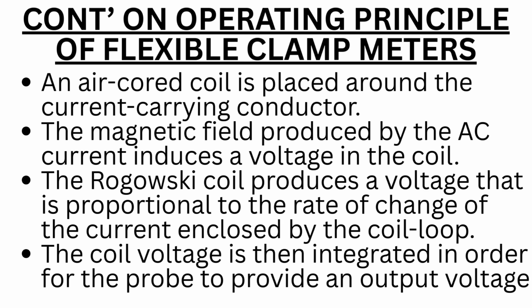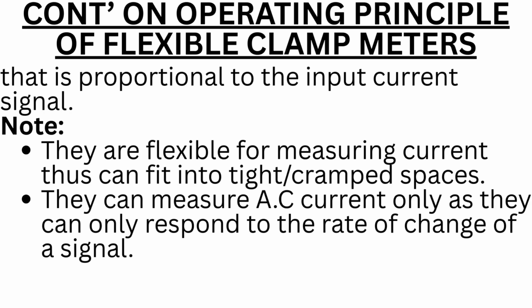An air-cored coil is placed around the current-carrying conductor. The magnetic field produced by the AC current induces a voltage in the coil. The Rogowski coil produces a voltage that is proportional to the rate of change of the current enclosed by the coil loop. The coil voltage is then integrated in order for the probe to provide an output voltage that is proportional to the input current signal. Note: they are flexible for measuring current, thus can fit into tight, cramped spaces. They can measure AC current only, as they can only respond to the rate of change of a signal.